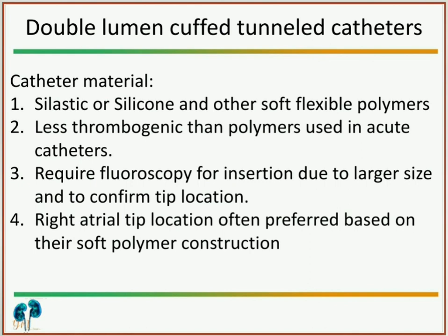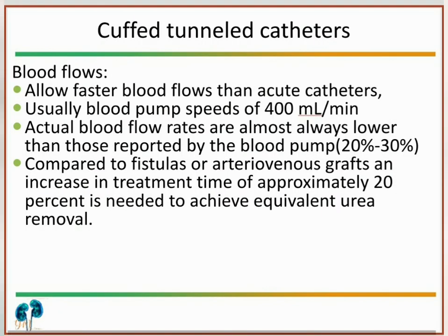The double lumen cuffed tunneled catheter is made up of silastic or silicone and other soft flexible polymers. Its advantage is that it is less thrombogenic than the polymer used for acute catheters. Insertion requires fluoroscopy due to its large size and to confirm tip location. In tunneled catheters, blood flow can be set faster than acute catheters, with pump speed around 400 ml per minute.